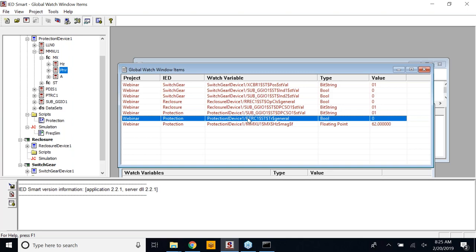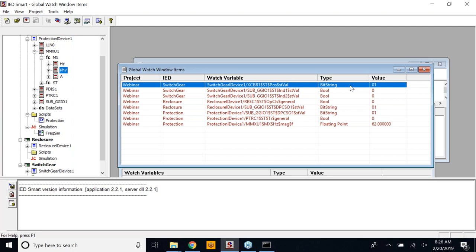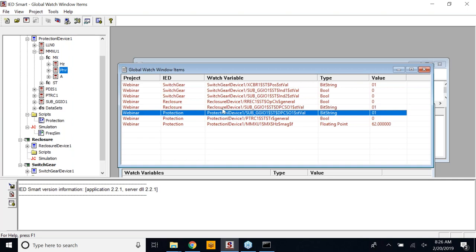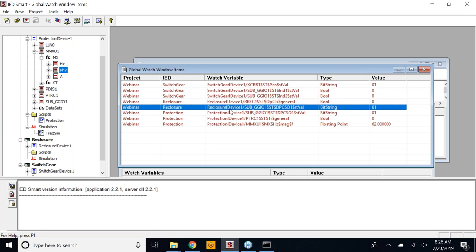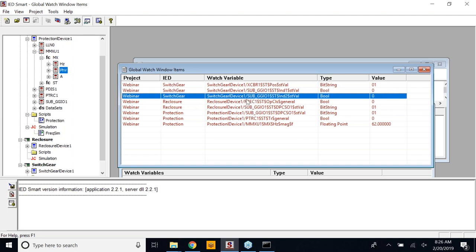This IED Smart can subscribe to the local Ethernet port and will be able to populate data from the remote IEDs using GOOSE subscription. Once the trip signal goes out, the same signal will be received by the switchgear. Indication 1 will be used to receive the trip signal from the protection device. Further, based on changes in the circuit breaker, the circuit breaker status will be sent out and the same will be subscribed by the other two devices — the reclosure device and protection device can subscribe to the circuit breaker status.